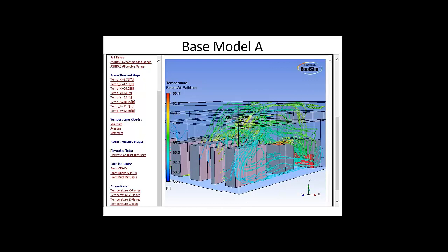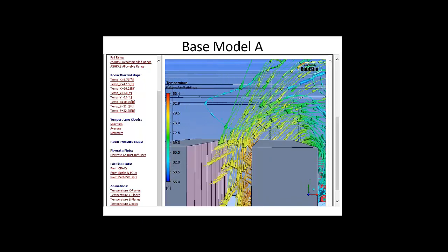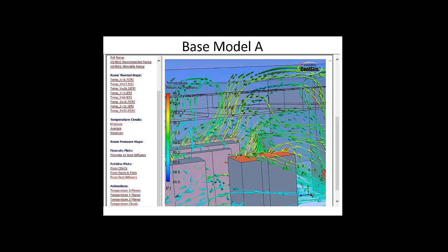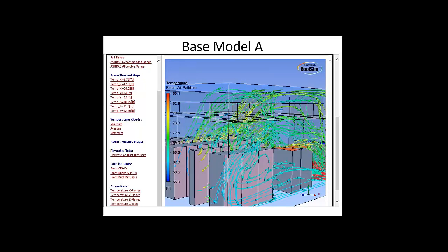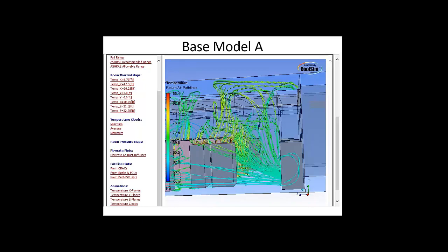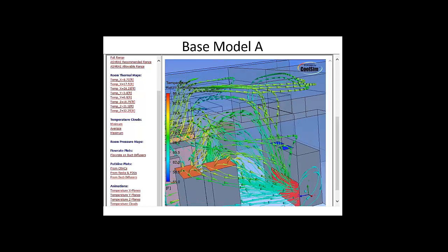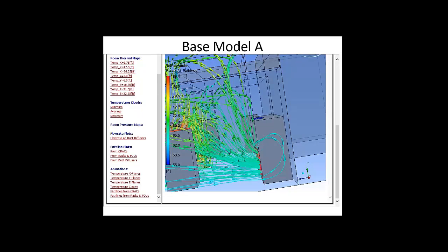If you take a look at these path lines, you can see the air. In this data center, the hot air, and this is hot air here, is flowing out of the back of these CRACs. We put arrows here now on the newest release of CoolSim so you can see the direction and the temperature. We're watching this air come across the room and have to go all the way back down and be sucked in. As it comes across hot, you see the color moving to cold, because as it gets near the bottom where the high density cool air is sitting, because it's heavy, it mixes and causes the return temps to cool off. So this is a fundamental problem. I see this a lot in these kinds of data centers, and that CRAC unit may be rated for a certain capacity, but it's certainly going to run well below that rated capacity.